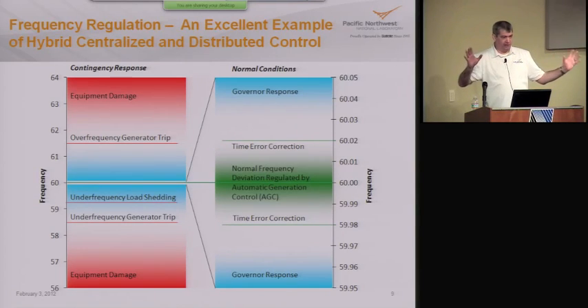And probably by then your grid will be broken up in islands, and that particular island that's generation deficient, if you ever trip a generator on underspeed, it means you're already in the throes of a blackout. So what do you do to prevent that? Well, you have the underfrequency load shedding that kicks in, and you drop load before you get to that point where you'd be tripping generators. And those set points are different in each of the interconnections. In the West, I'm more familiar with that. The first set point is 59.3. And then there are time delays for each block of underfrequency load shedding. And so that's to prevent you from getting into that underfrequency generator tripping regime.